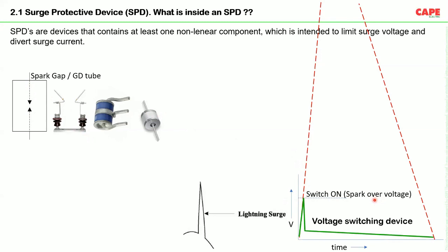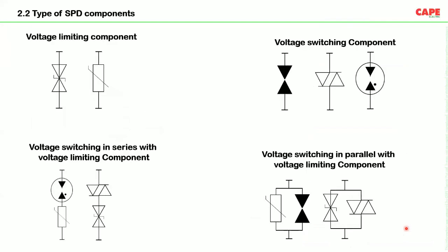It acts like a switch. Up to its spark over voltage it does nothing, and once the voltage reaches the spark over voltage, the device suddenly works like a switch and connects both the terminals. As a result, the transient over voltage between the lines, or wherever it is connected, becomes almost zero. So there are two kinds of devices, with respect to characteristics, which are used as SPDs. One is the voltage clamping type device, and the other is the voltage switching type device. Now, what you are seeing in the picture are the SPD components.